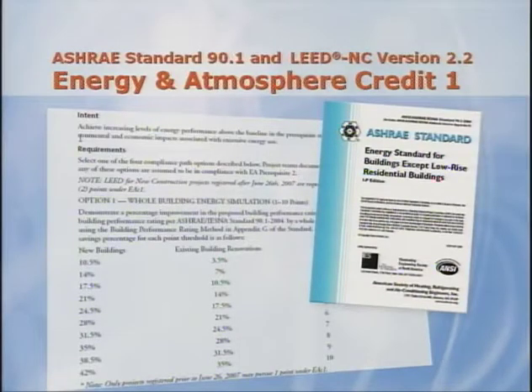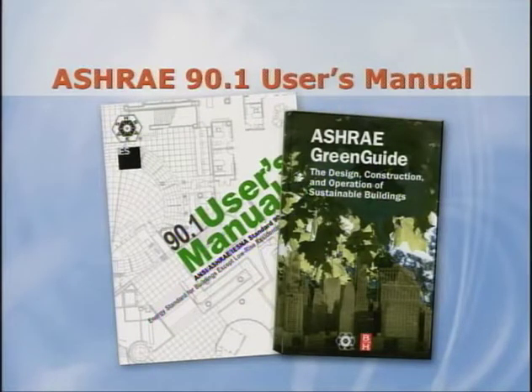Right. As we saw here, HVAC improvements aren't the only building systems that can contribute to this improvement. The building envelope and internal loads, such as lighting, can have a significant impact on improving energy performance. Modeling of the building will be required to determine the expected energy cost savings for the overall improved building. But the effort put into modeling high-performance building options can yield a significant reduction in energy use. The ASHRAE Green Guide, the Advanced Energy Design Guide series, and even the standard 90.1 User's Manual are great resources of information that offers approaches and suggestions on how you can modify your design to improve energy performance.